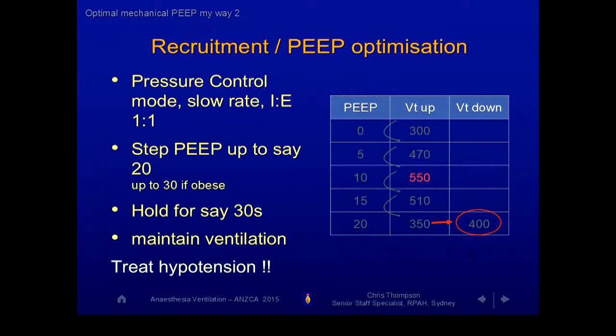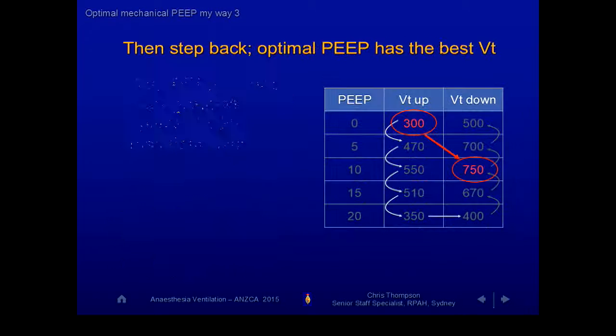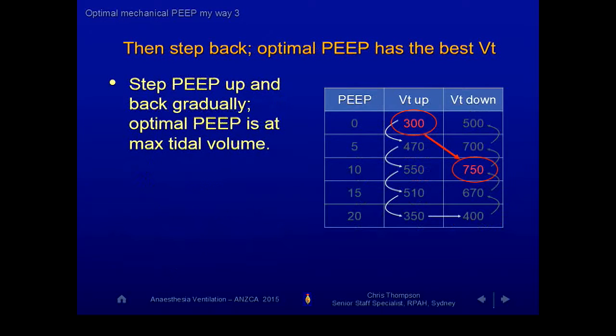Well, one way is to step the PEEP up with a constant pressure difference. Just ramp it up and look at the tidal volumes. And you will see something like this, where as you ramp up the PEEP, keeping the pressure the same in pressure control, the tidal volume gets bigger and bigger and bigger up to a point, and then it gets smaller because you've overstretched them. Now, if you leave them up there for a while, they'll recruit a number of ways. This is a simple way of doing it. And then you can come back the other way. And when you come back the other way, you'll find something remarkable, that at some value, 8 or 6 or 4 or some value, the lung will be way stretchier than it was before. And that's because that lung is now being recruited and you're now able to ventilate it.